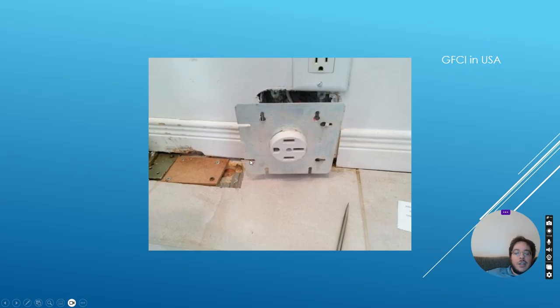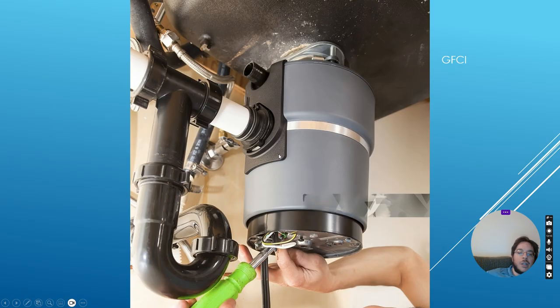Now, like I said, you need a receptacle for your oven. So the oven receptacle is a 2-pole 50 amp receptacle. So it's got ground, hot, and neutral. And you need a minimum of a 40 amp breaker, but you can do 50. You just gotta make sure whatever rating of breaker you put, you match the wiring ampacity so that you don't melt the wiring before the breaker trips. Now, in the United States, this has to be a GFCI. In Canada, it does not, but it does have a special rule, which is the ground must face either the left or the right. You can't have the ground facing the bottom or the top. The ground is a U-shaped hole.